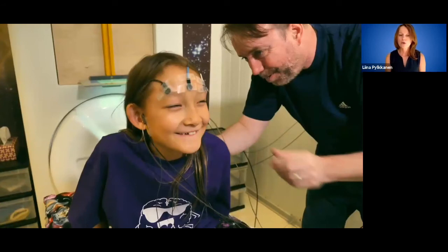It's very important that once you're in the MEG machine, we know exactly where you are with respect to the sensor space. So for that reason, we place little coils on your forehead and next to your ears on points that we digitized in the course of the 3D scanning of your head shape.